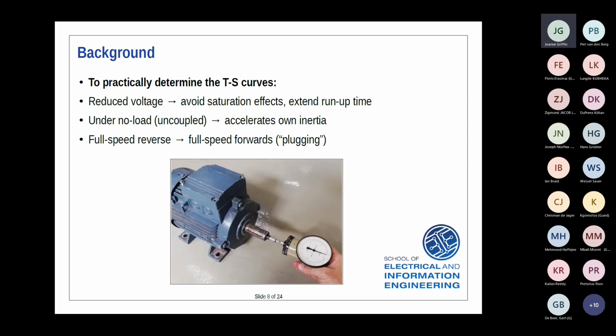Right, so I've got a picture here of a handheld tacho. We don't do it this way. We use a small tacho generator to produce a signal. The reason I put the photo in here is it's critical. One of the problems of doing it with a handheld device is that it's almost impossible to get the tachometer in line with the shaft.